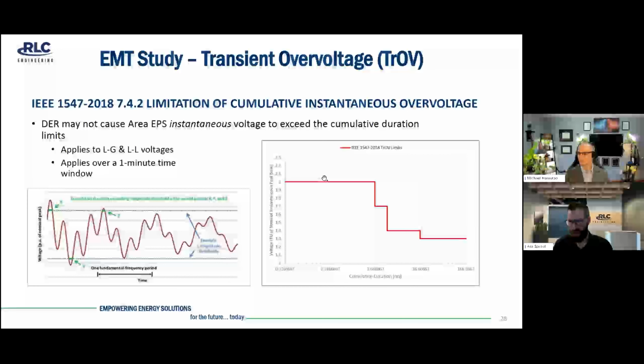And it's a little confusing, but by this I mean these blue horizontal lines here on the left correspond with the various magnitude thresholds that are shown here on the right. So 2 per unit, 1.7 per unit, 1.4, et cetera. The durations that each threshold is violated are summed. So in this case, that would be this X, this Z, and this Y. And then you essentially obtain a performance curve on how your project performed under those scenarios. And I'll show an example slide shortly to give you an output of what our evaluation would provide. But for this evaluation, both line-to-ground and line-to-line voltages are monitored. And these are measured over a 1-minute time window per 1547.